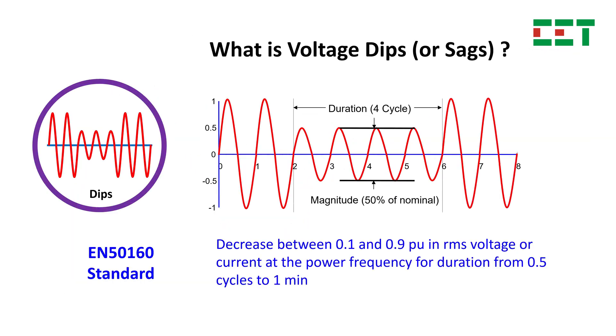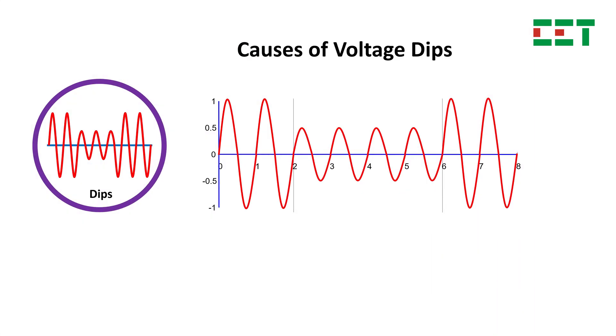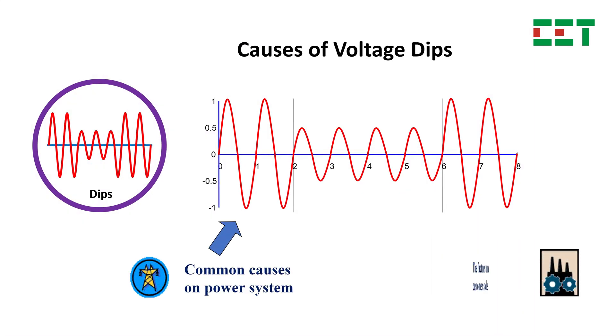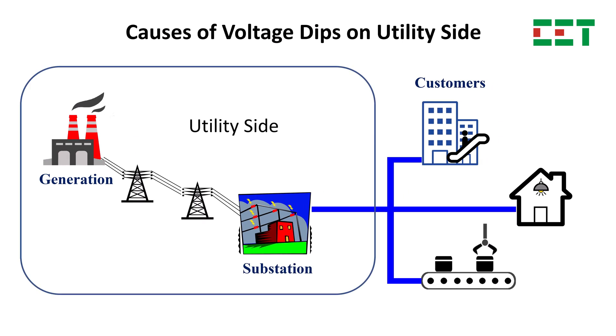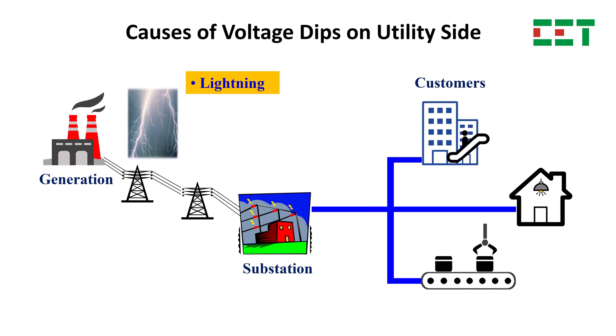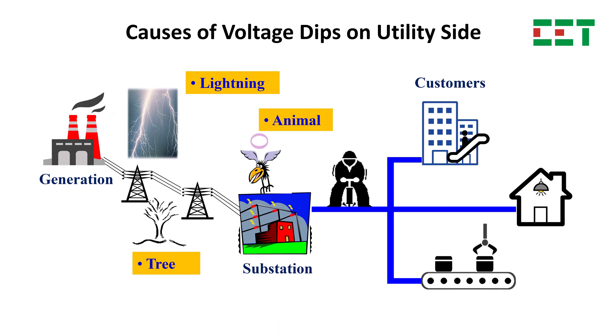According to the EN50160 standard, voltage dips are short-term drops in voltage. They can occur due to disturbances on the utility side, for example, ground faults from fallen trees, lightning strikes, or sudden load changes.